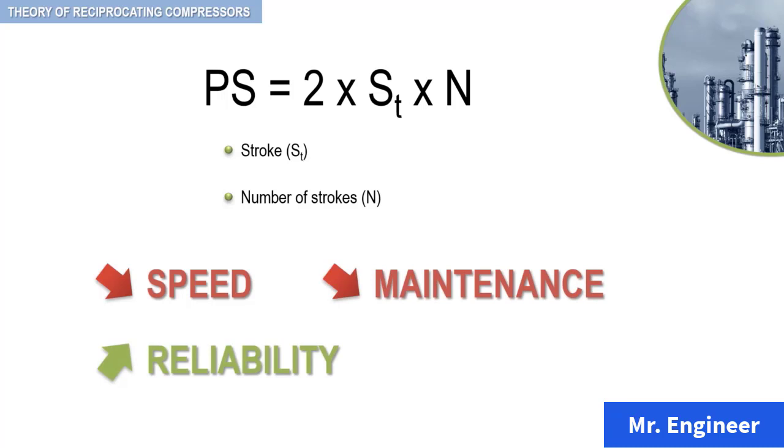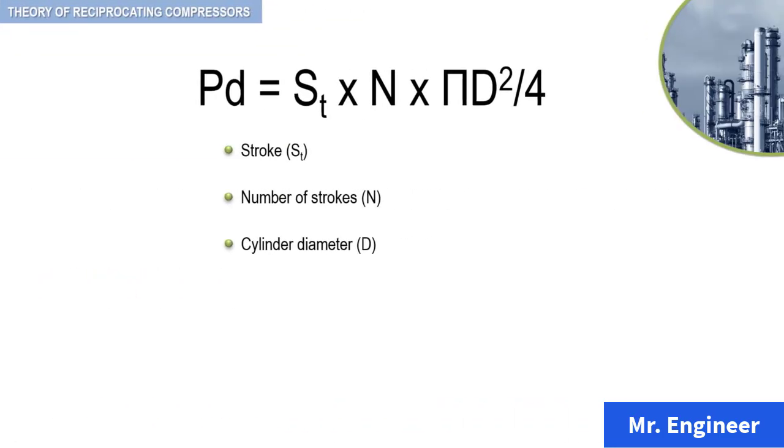The relationship given by the piston displacement, as seen in a previous video, which is reminded here, defines the size of the cylinder. Therefore, if the speed is reduced to lower the piston speed, then the diameter of the cylinder must increase to compensate for the lost displacement in order to maintain the same capacity.